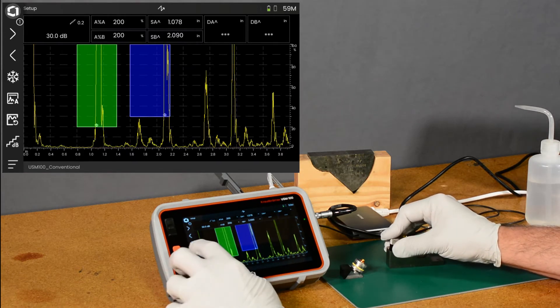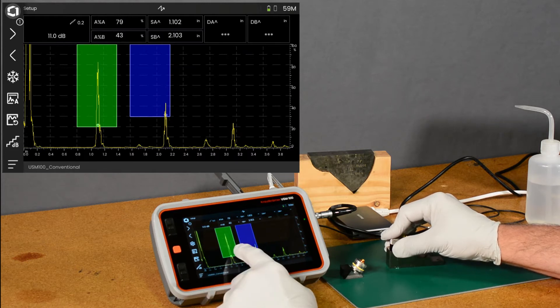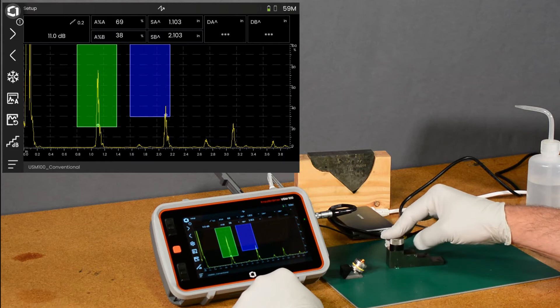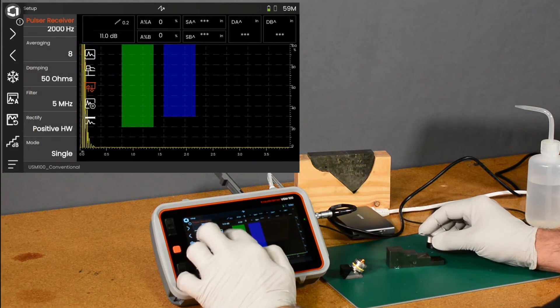So we can take our gain down some. We'll use the auto 80 function to get the gain on the 1 inch block in gate A nicely at 80%.